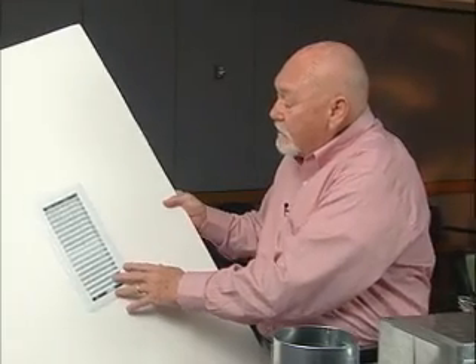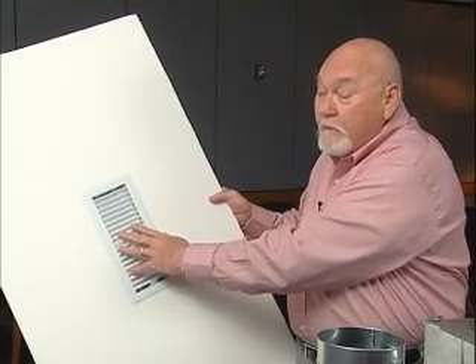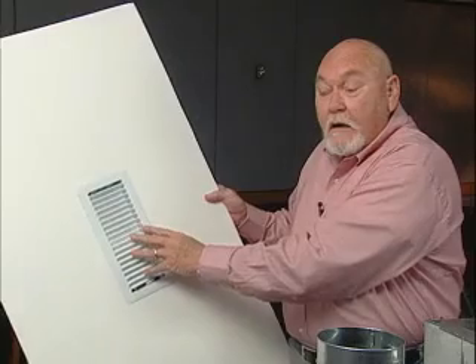A little thing that you might do to determine if you need to have your unit serviced is take a thermometer and put it at the register or the vent. A lot of you call it the vent. Put it in the vent or close to the vent. If the temperature of the air coming out of the register is 55 to 60 degrees, your equipment is working properly. If it's in the 70 to 80 degree range, you need to have your unit serviced.